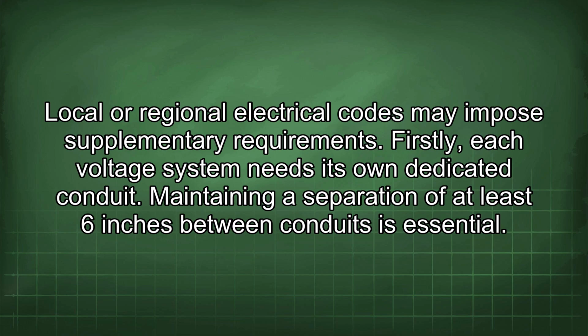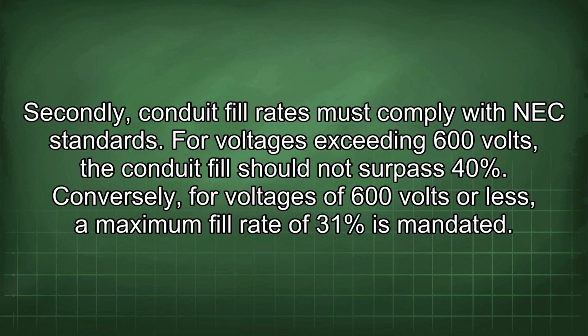Firstly, each voltage system needs its own dedicated conduit. Maintaining a separation of at least 6 inches between conduits is essential. Secondly, conduit fill rates must comply with NEC standards. For voltages exceeding 600 volts, the conduit fill should not surpass 40%. Conversely, for voltages of 600 volts or less, a maximum fill rate of 31% is mandated.